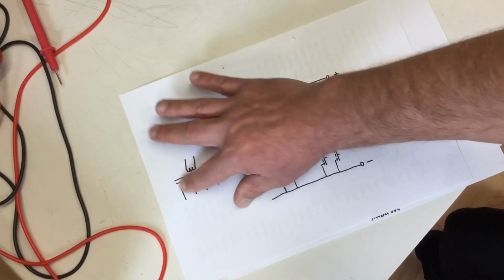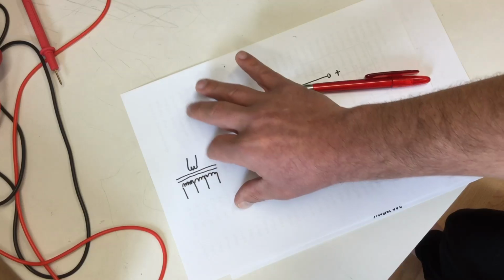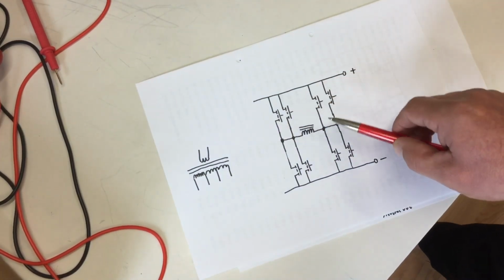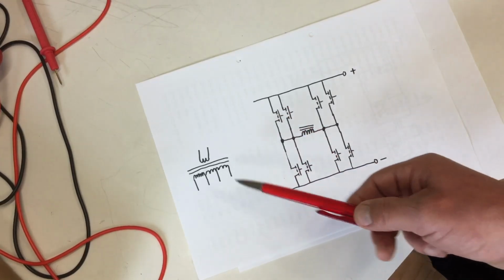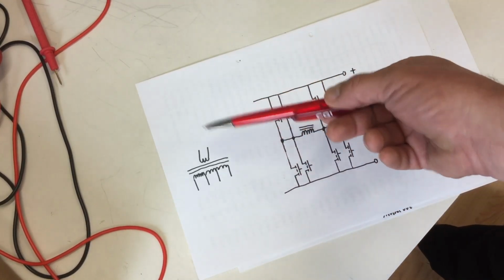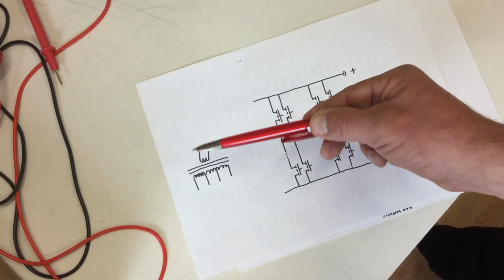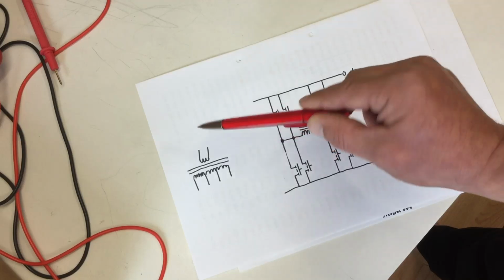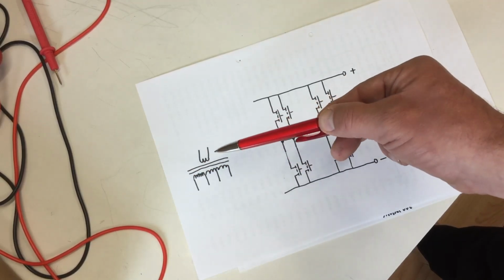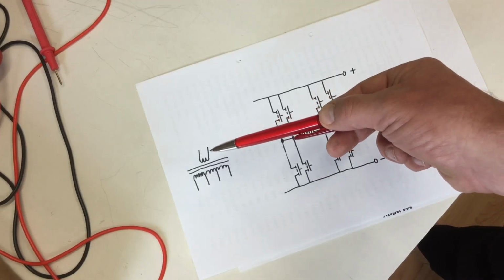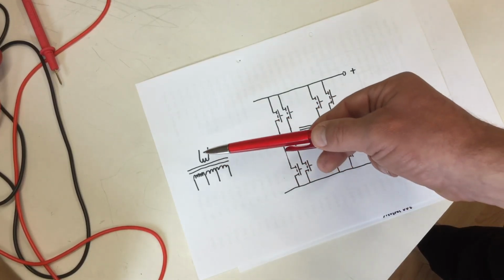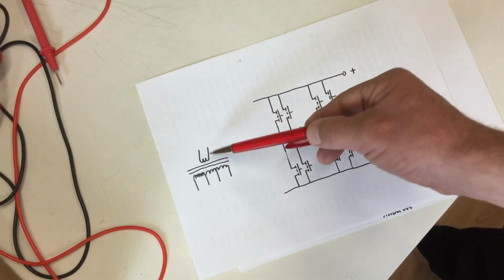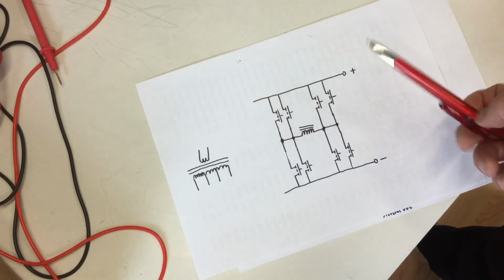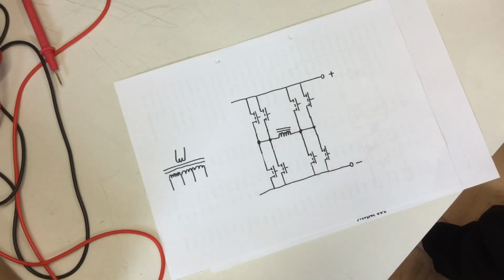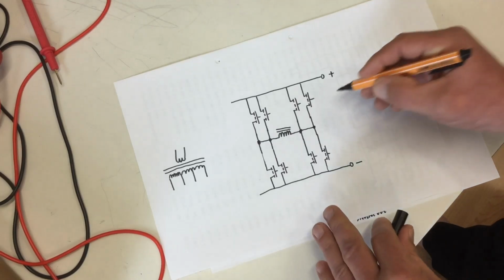So up to now we just looked at the autotransformer side, but basically it's a combined transformer and autotransformer. If the mains voltage fails completely, since it's a UPS, they take the battery power and induce some AC through that secondary winding, which in that case becomes a primary winding. I guess they also use that winding to charge the batteries.